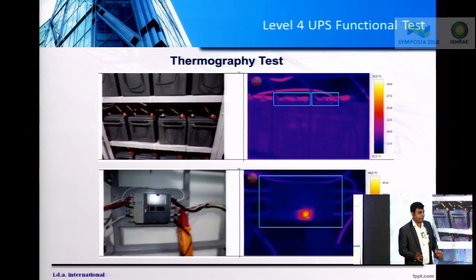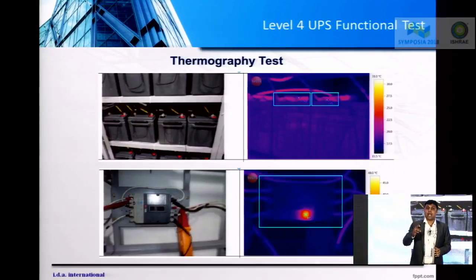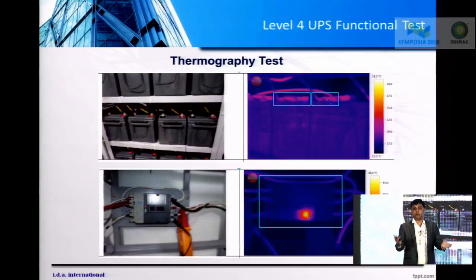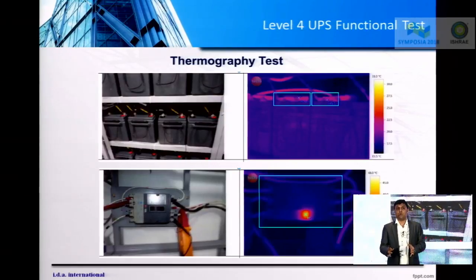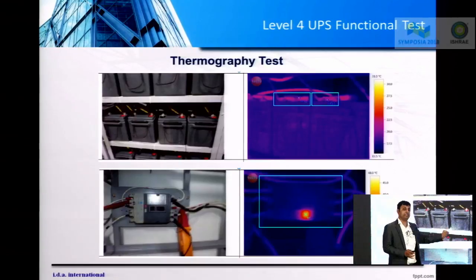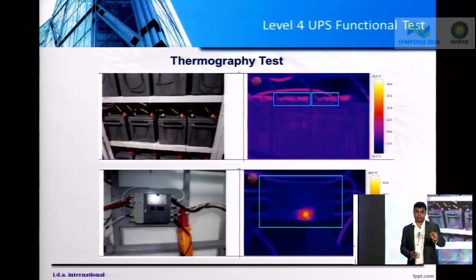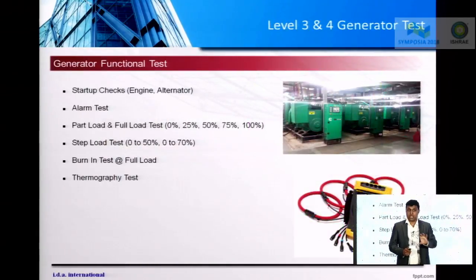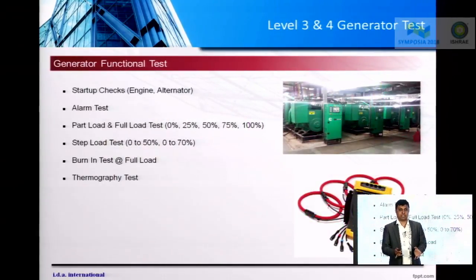And it is through my practical experience I can say that out of a number of UPS that we have tested during the battery discharge test, we could identify 5 to 10 batteries which are faulty and have to be replaced. If you don't replace faulty batteries, it could drastically impact your battery backup time. So this was some of the example of how we carry out the performance test of a UPS.